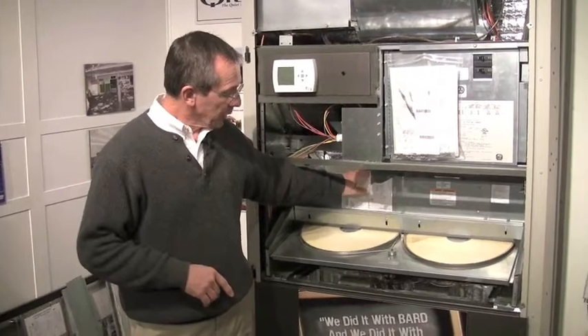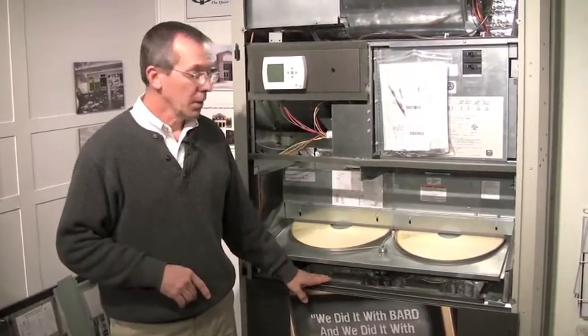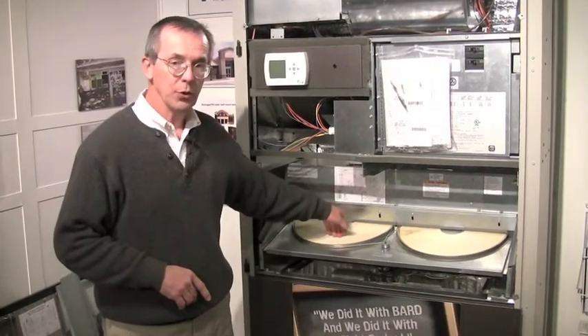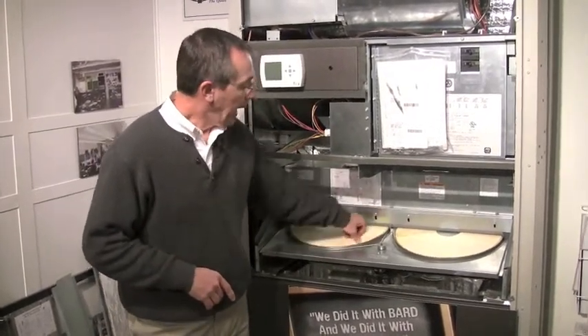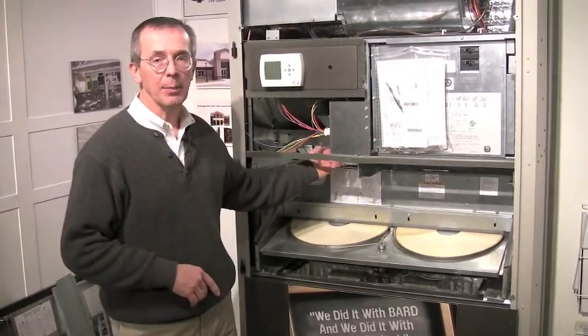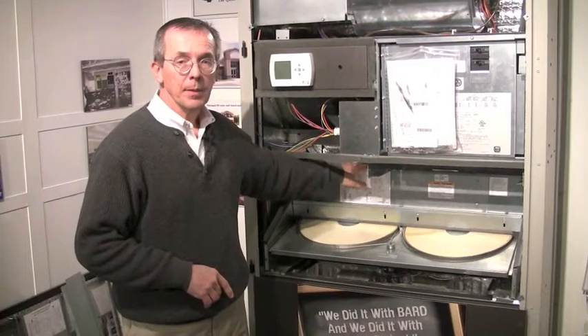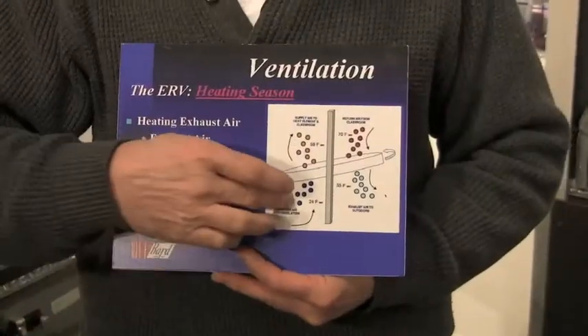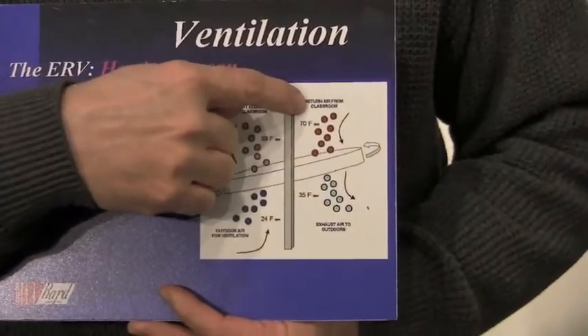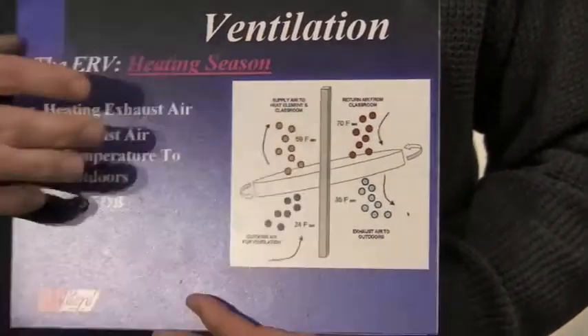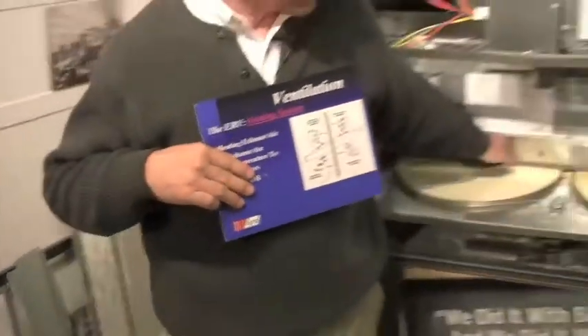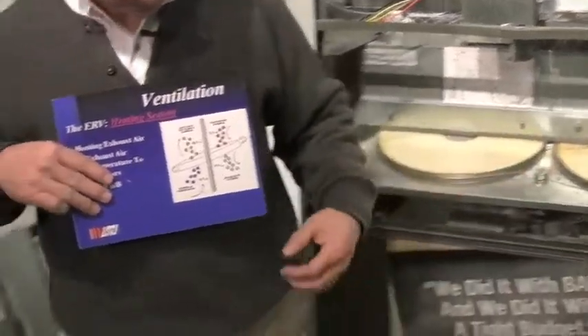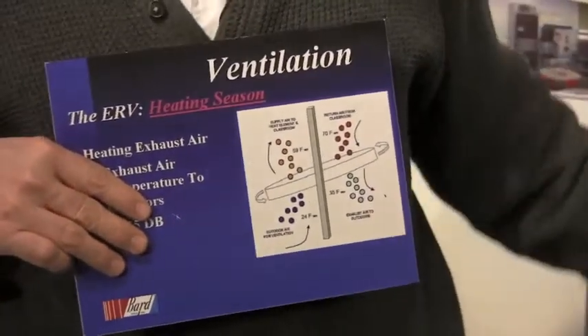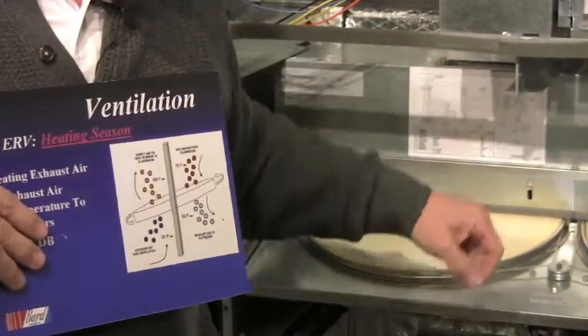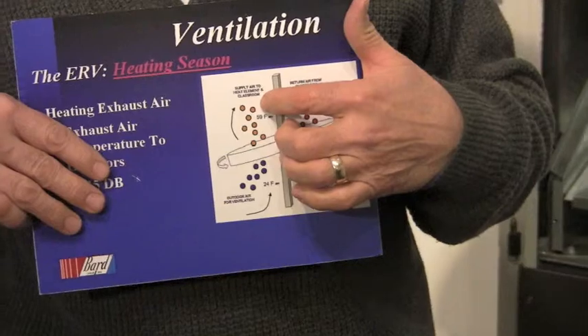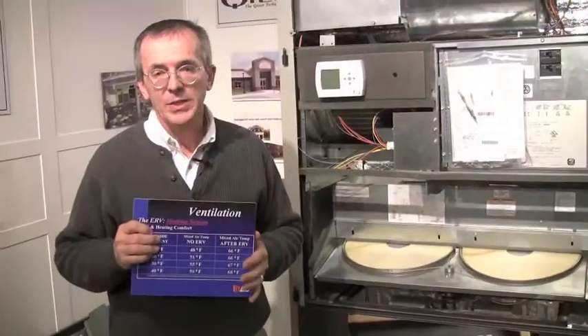Let's say we're setting at 300 intake and 300 exhaust. So 300 CFM is going to be pulled down through the wheels. It picks up the energy. As it turns, the outside air comes up through the wheel with this blower and picks up the energy from the wheel. To give an example, 24 degrees outside, 70 degrees on the inside of the classroom. The wheels are turning. This bar here represents this bar on the wheels. So when the air comes off the top of the blower here, you're going to go from 24 degrees up to 59 degrees. I'm sure you know what mixed air temperature is.